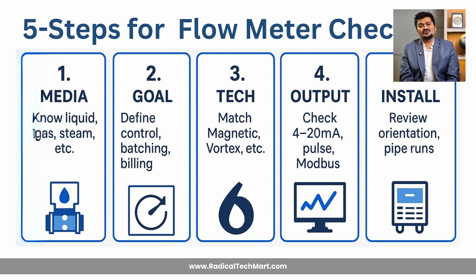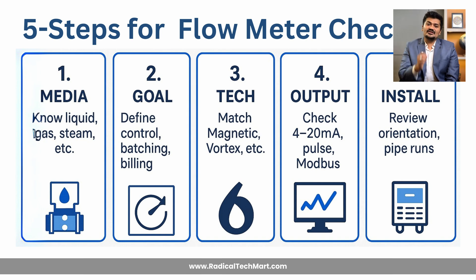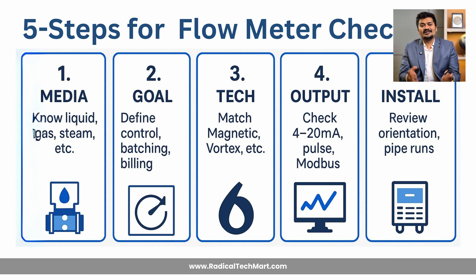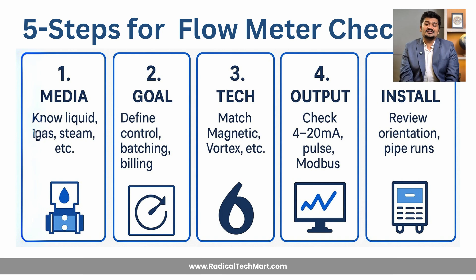First, know your media — liquid, gas, steam, or slurry. Second, define the goal — control, batching, monitoring, or billing. Third, match the technology — magnetic, vortex, and so on. Fourth, check your outputs — 4 to 20 mA, pulse, or MODBUS. Fifth, review your installation conditions — orientation, pipe runs, and space. Still unsure? Drop your application in the comment section and we will personally guide you.